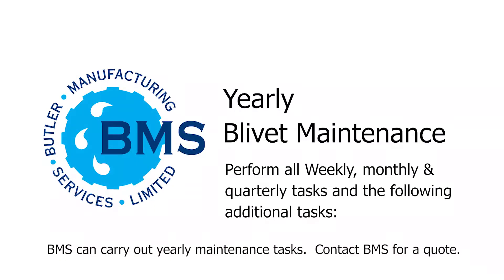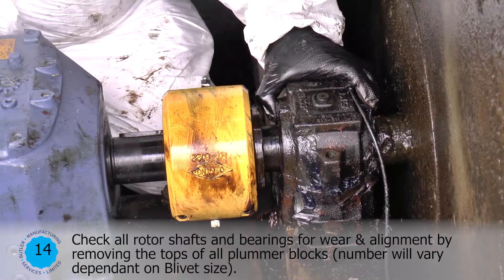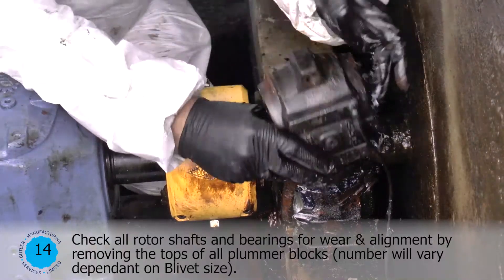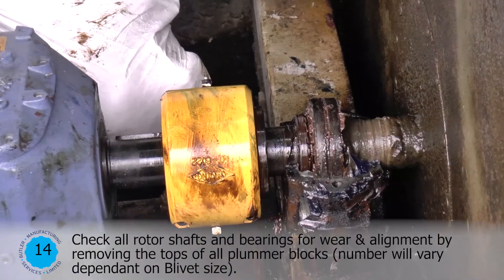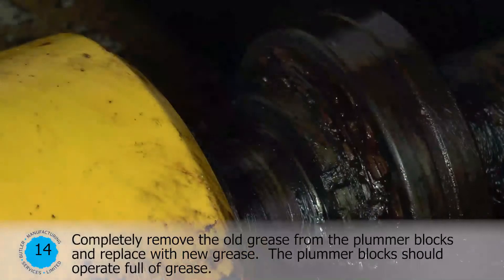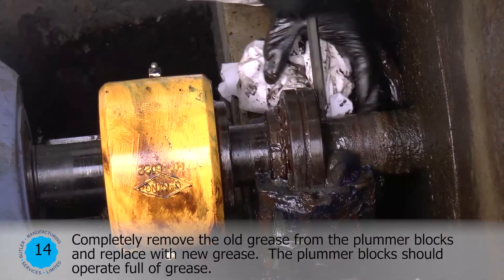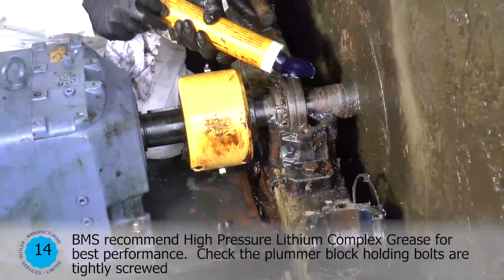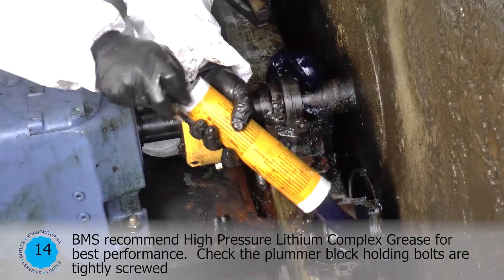Yearly Blivet Maintenance. Perform all weekly, monthly, and quarterly tasks and the following additional tasks. BMS can carry out yearly maintenance tasks — contact BMS for a quote. Check all rotor shafts and bearings for wear and alignment by removing the tops of all plummer blocks. Number will vary depending on the blivet size. Completely remove the old grease from the plummer blocks and replace with new grease. The plummer blocks should operate full of grease. BMS recommend high pressure lithium complex grease for best performance.